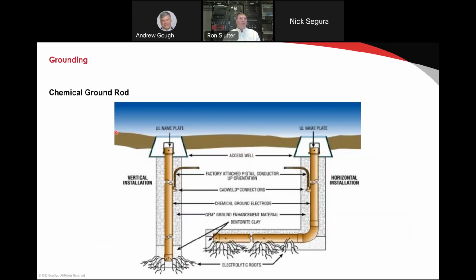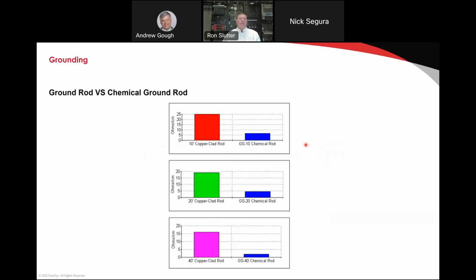To get around that, I say use a chemical ground rod. So this is 100% copper tubing, 3 inches wide, goes all the way to the surface, gets you below the ground frozen depth, and install a trench with this type of installation. This is a cost-effective way to get very good grounding. So you can see a reference between a typical 10-foot ground rod and a chemical rod, significant enhancement in its capability. And it only gets better with time. It doesn't wear out like a typical ground rod. So this is a 10-foot, 20-foot, and 40-foot installation. With a 40-foot installation, we can get down below 2.5 ohms. Typical ground resistance measurements now are typically 5 ohms or less. That's what we're looking for.